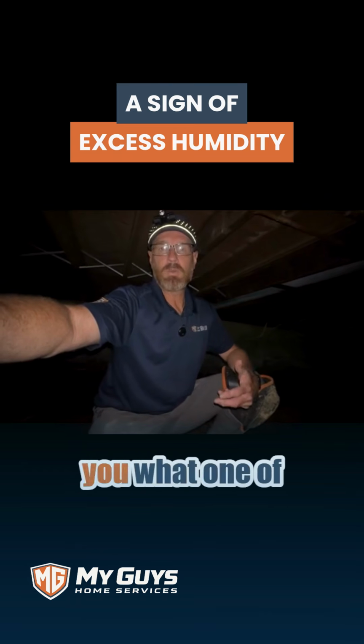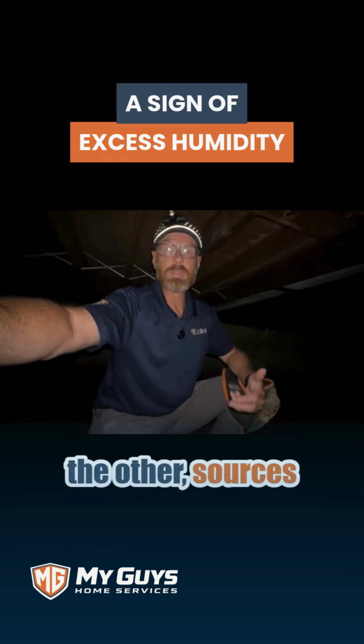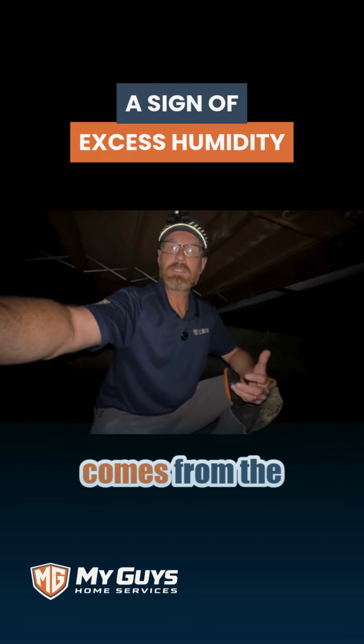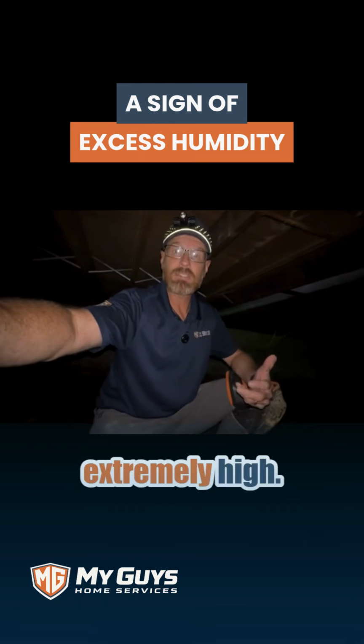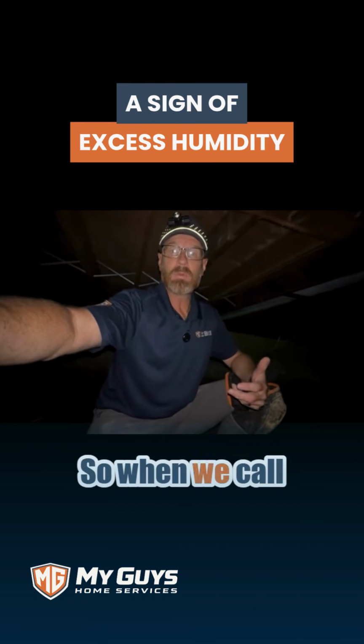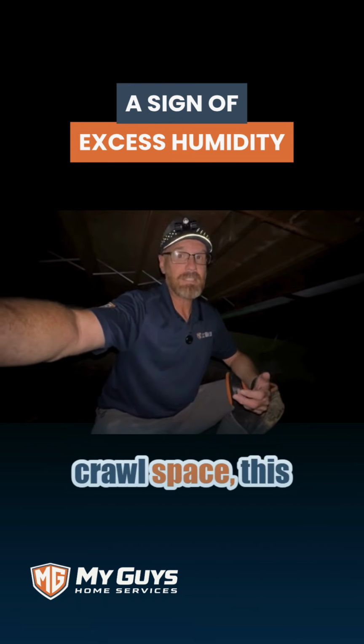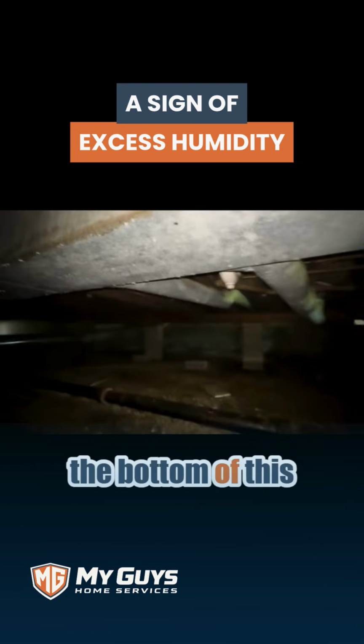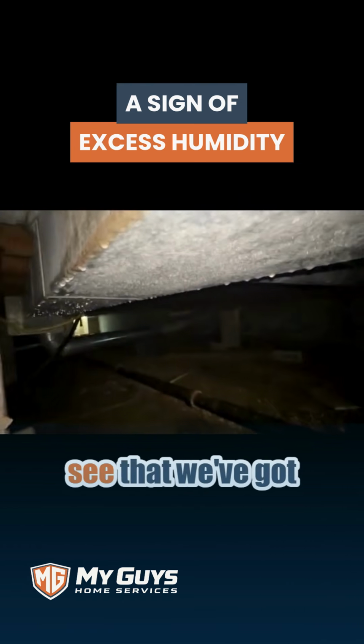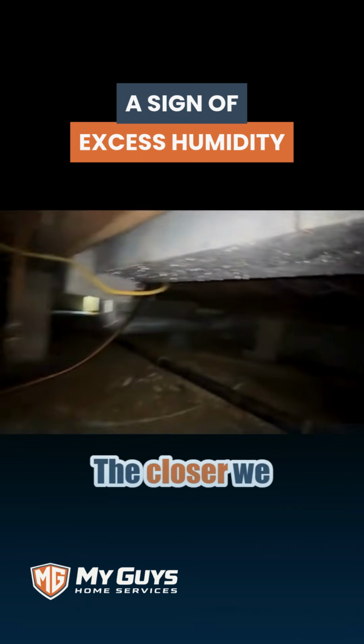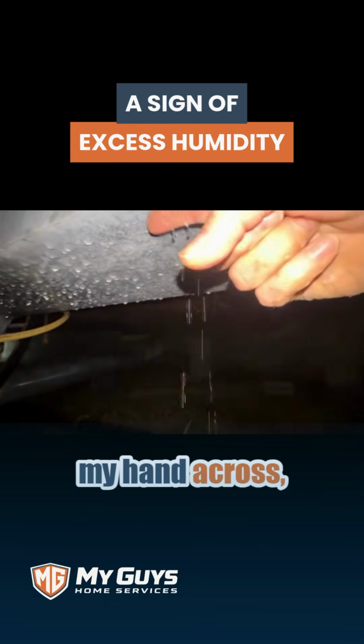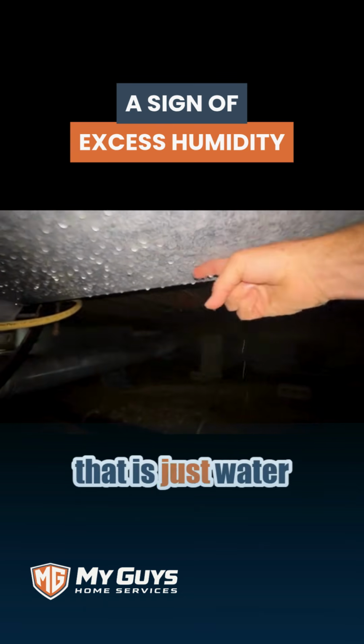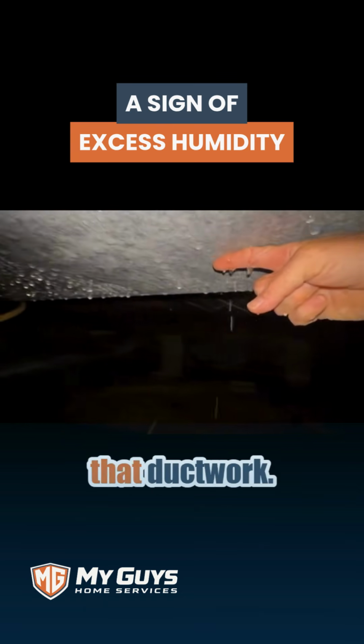I want to just show you what one of the other sources of moisture in a crawl space is, and it comes from the humidity being extremely high. So when we say it can rain in your crawl space, this is what we mean. I'll show you here. When you look at the bottom of this ductwork, you can see that we've got water droplets coming off of it. I'll come around here. The closer we get, the more pronounced that is. So if you see, I run my hand across, that is just water pouring off of that ductwork.